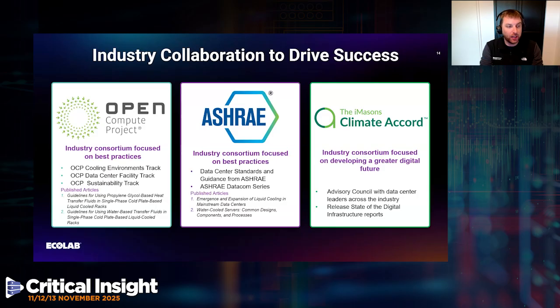So what you could do today already is check out some of the materials we've published, for example with the Open Compute Project, on how to start up a loop, how to flush a loop, and considerations when using propylene glycol-based systems versus water-based systems. We also do this with ASHRAE, and we're part of the IMASons, where it's important to consider that the chemistries you employ are safe to use and not under environmental constraint. You can find our contributions under the name Nalco or Ecolab on many of these platforms, and we invite you to download them there. Often it's for free.